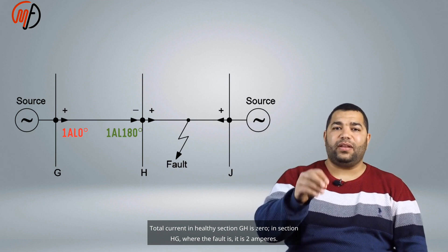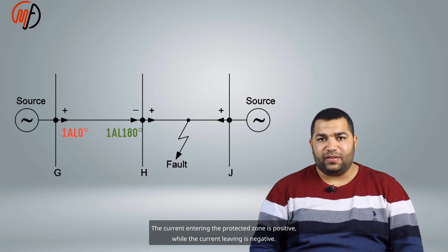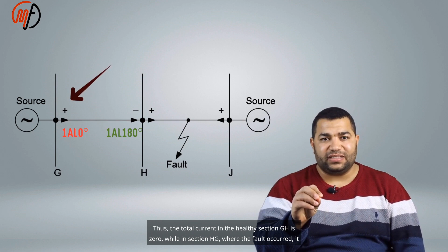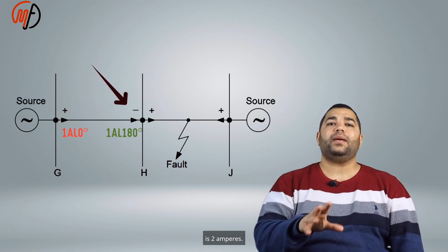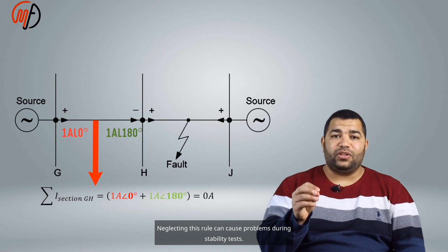This rule aligns with global systems for electrical network analysis, emphasizing polarity's role in current flow direction. Both resultant currents will remain 0. The current entering the protected zone is positive, while the current leaving is negative. Thus, the total current in the healthy section GH is 0, while in section HG, where the fault occurred, it is 2 amperes. Neglecting this rule can cause problems during stability tests.